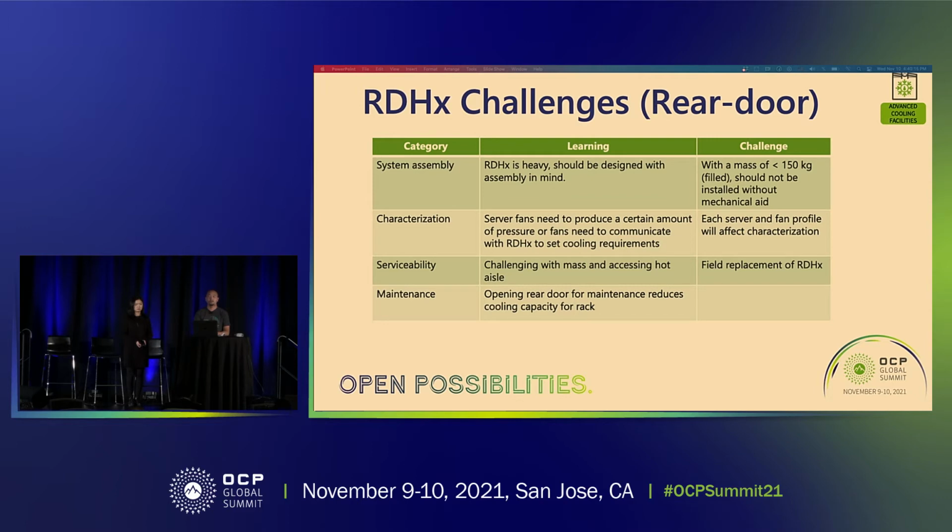One of the challenges in that is every single rack deployment and rack configuration at the L11 level would have to be tested to make sure that whatever servers are being put in with the rear door heat exchanger work properly together as a total system.